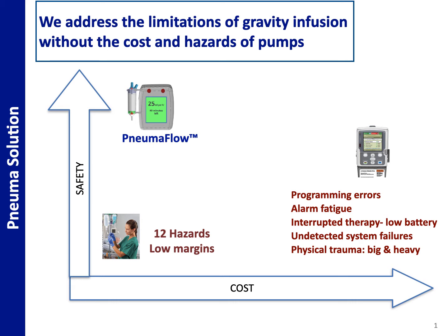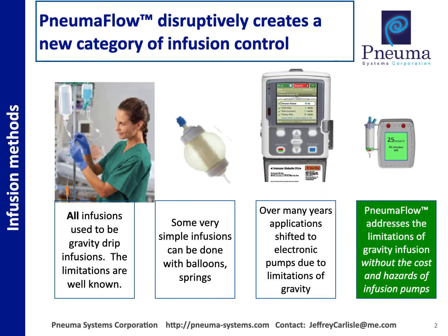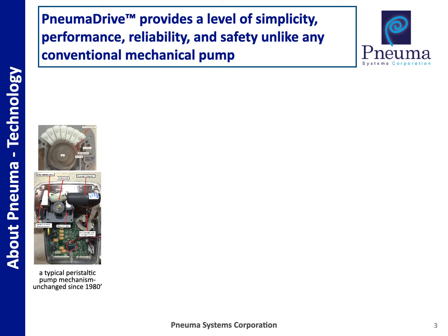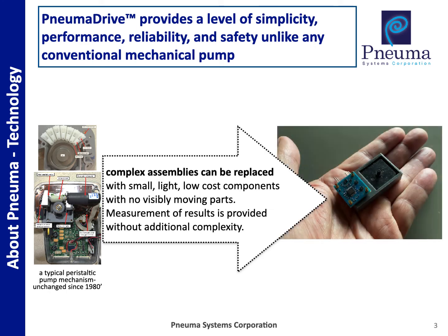So from a big picture point of view, we looked at current infusion pumps and we looked at gravity infusion. And the concept here was to avoid all the well-known hazards of gravity infusion and avoid the new hazards caused by traditional infusion pumps. So we've created a new category of infusion devices, not gravity, not a passive pump like an elastomeric or a spring-based pump, not a conventional electromechanical peristaltic or syringe pump, but really an entirely new category of pump. It's based on a technology that replaces dozens or hundreds of electromechanical components in an infusion device with a single platform that appears to be solid state, where there are no moving parts, it's quiet, it's inexpensive, and simple.